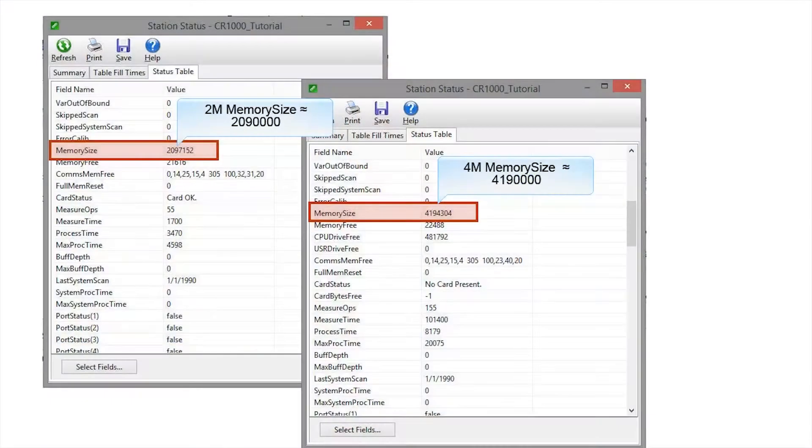We'll take a look at the second method of sending an OS to a data logger. Using this method, you can send the OS to a remote data logger — one that is on a telecommunications link. CR1000 and CR800 data loggers with two megs of SRAM cannot use this method. You will need to use the Device Configuration Utility and be directly connected to send an OS to those data loggers. Data loggers manufactured before September 2007 have a 2-meg memory. You can also check the memory size field in the status table.